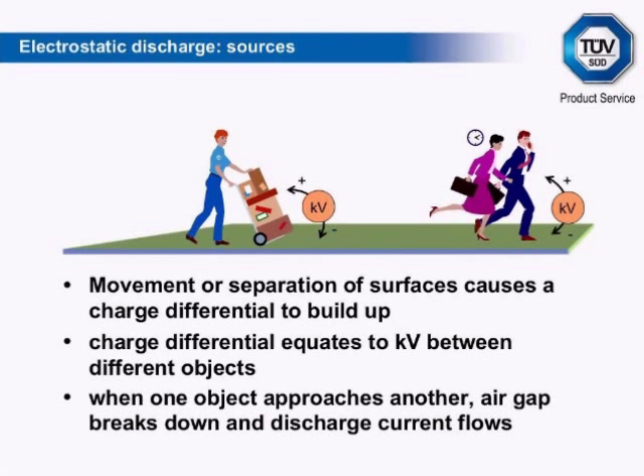The severity levels in IEC 61000-4-2 represent four categories of environment depending on their likely minimum relative humidity and the presence or absence of static-generative materials. Level 1 is 35% minimum relative humidity with anti-static control and a 2 kV contact or air discharge, going right up to level 4, which is 10% relative humidity, a synthetic-rich environment, with 8 kV contact and 15 kV air discharge.